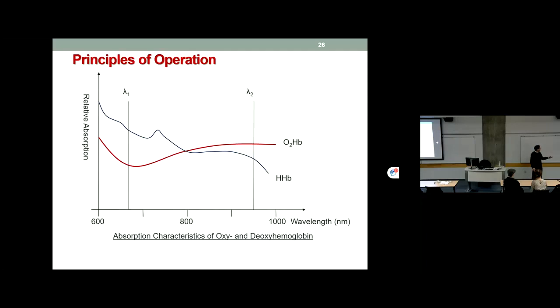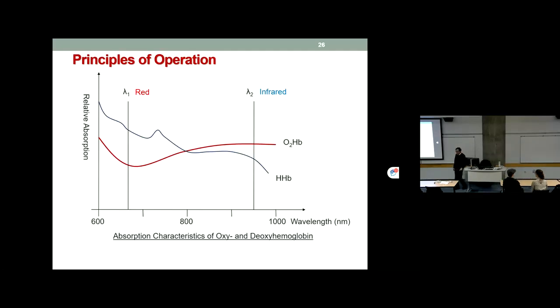When I turn on the device, you can only see one color — red — because the other wavelength is infrared, which is invisible to the human eye. So the device uses two narrow beams of light: red and infrared. Getting into the math: we have two substances (oxyhemoglobin and deoxyhemoglobin) and two wavelengths. We shine red light through and establish one equation using Lambert-Beer law with two concentration unknowns. We then shine infrared light through and get a second equation.